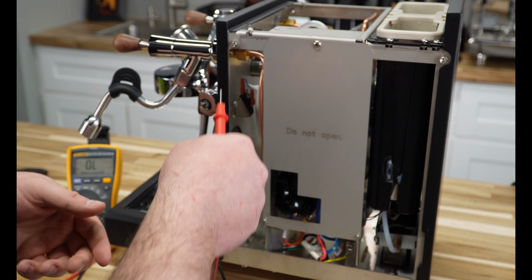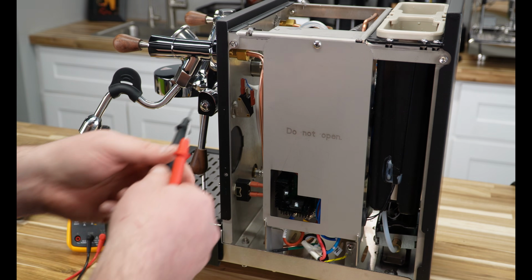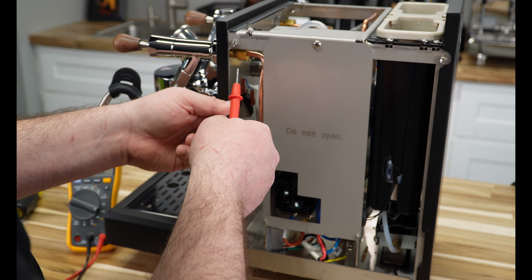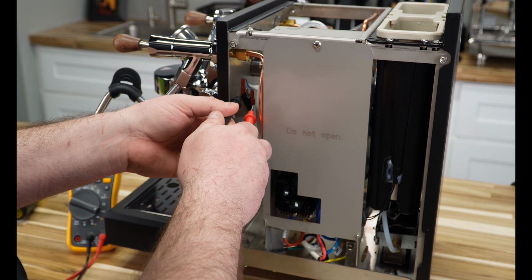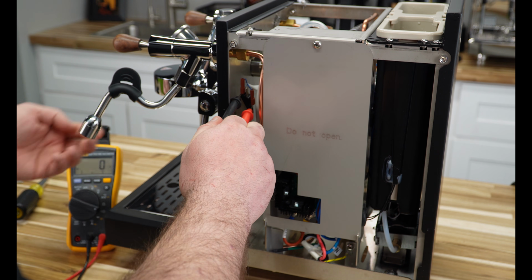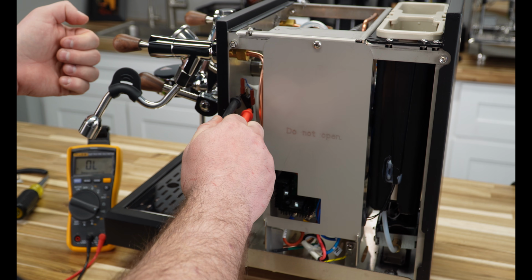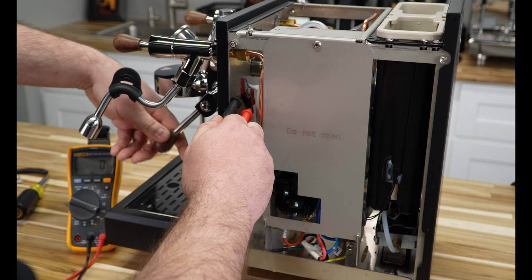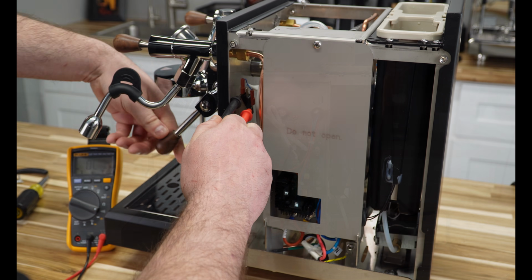If this were to ever break, it's not going to just run freely. They actually have it set up in a fail-safe mode. If I put these in the down position, we'll hear a tone, and when I raise it up, the tone stops. So we know this switch is in good condition.